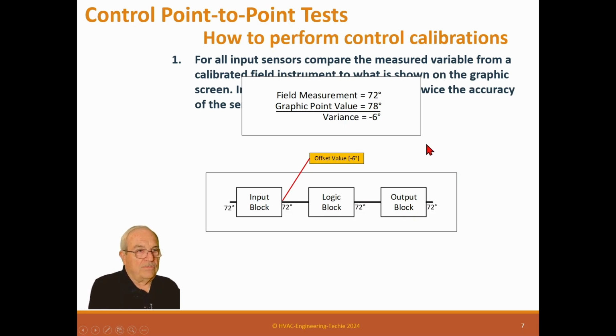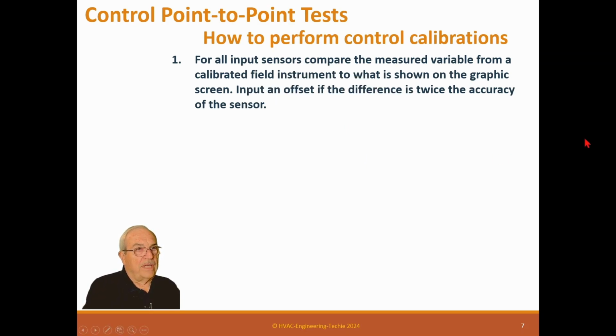Now that brings up another subject: not all programmers are created equal. And I've done jobs where on day one we were there, and I was asking the technician to do me an offset, and he said, no problem, what do you need? And he did it fine. The next day, it was a different technician because the other one was busy, and I said, I need to do an offset. He said, our system, we can't do offsets. I said, pardon? Oh, no, we can't do offsets. Yes, you can. Oh, no. I said, the guy yesterday did one, and I got those blank stares in the headlights because he did not know how to do an offset. And so you have that knowledge problem, but they're expected to know how to do this. So that's how an offset is done in a system.